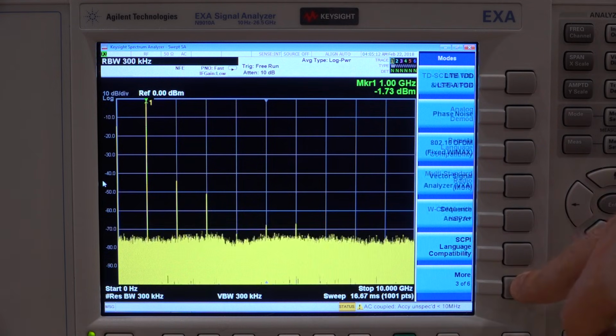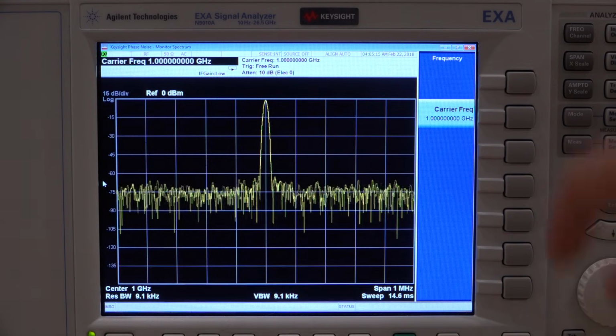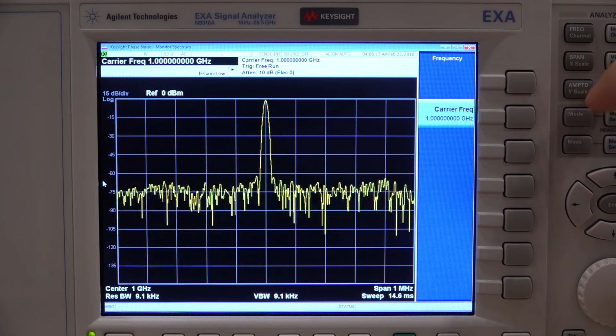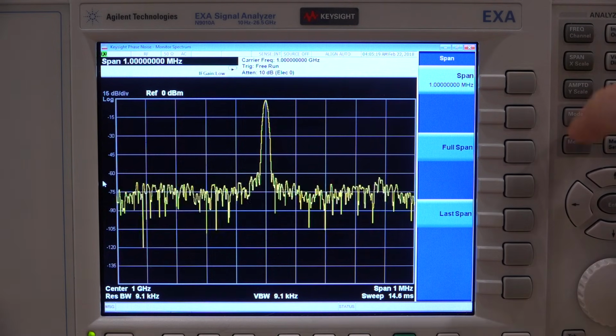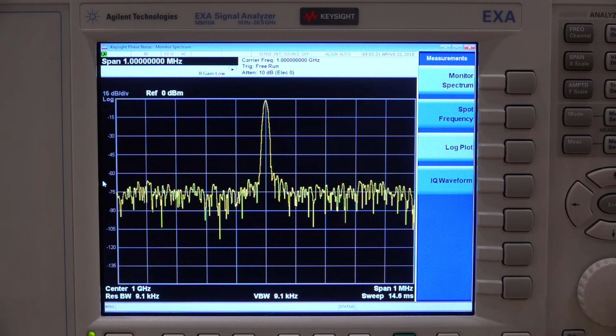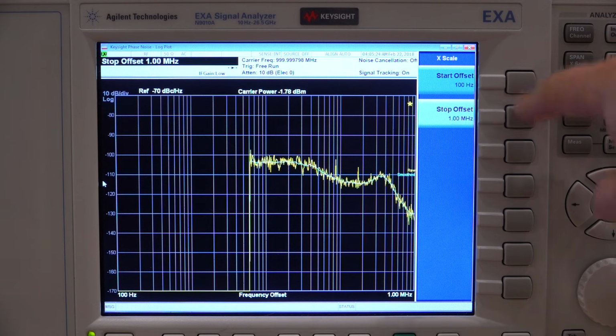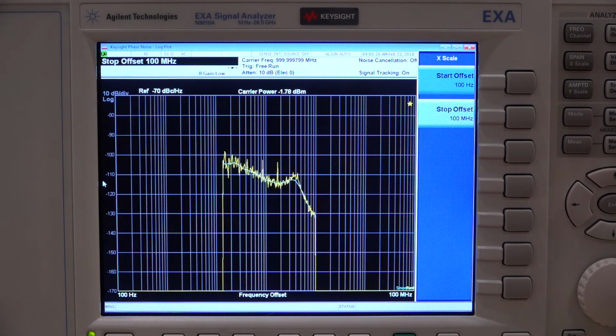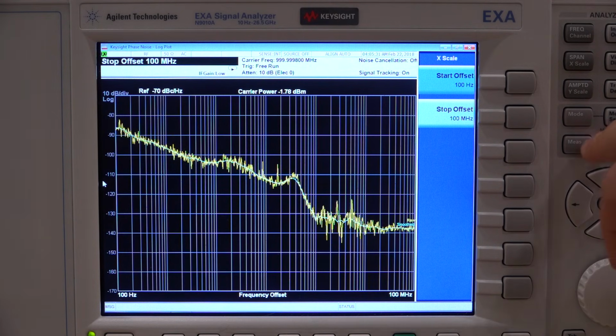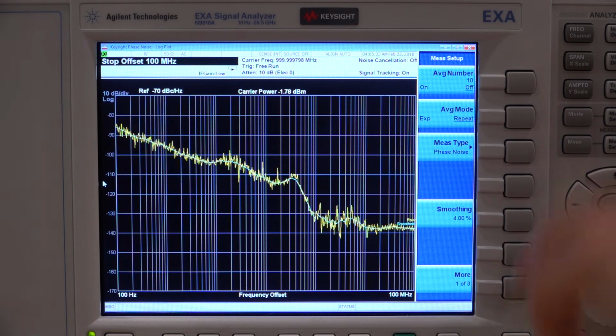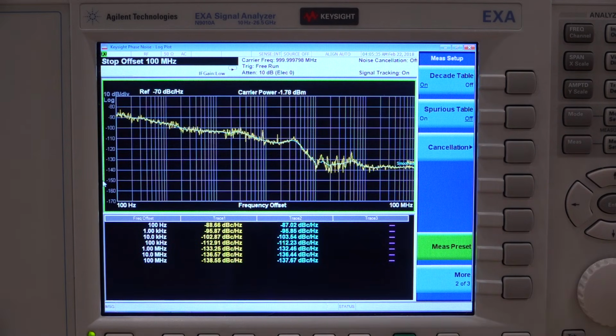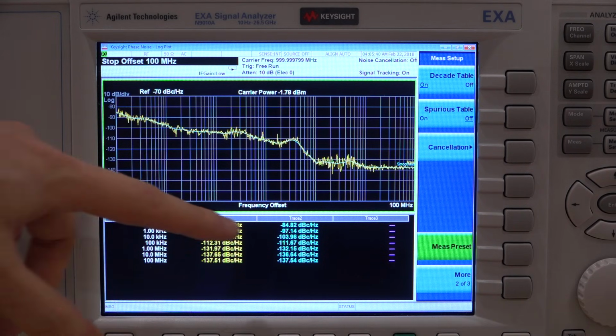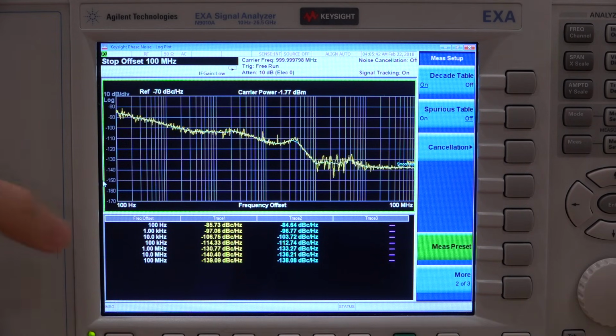Let's change the mode here to phase noise. And it's already at 1 gigahertz. So let's go ahead and change the mode to a log plot, and let's measure a wider frequency span up to 100 megahertz. And there it is. Let's enable our table. There we go. So as you can see, at a 1 kilohertz offset, our phase noise is about -87 dBc per hertz, and at 1 megahertz offset it is -132 dBc per hertz.